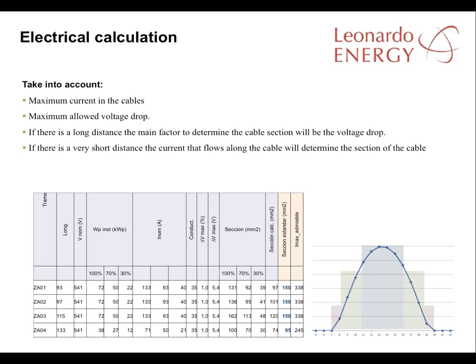In calculating electrical issues, it's very important to take account of the maximum current in the cables and the maximum allowed voltage drop. If the cables cover a long distance, the main factor to determine the cable section will be the voltage drop. But if the cable covers a very short distance, the current that flows along the cable will determine the section of the cable.